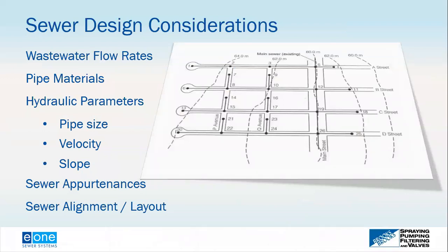When looking at design considerations, there are many similarities and differences between gravity sewer systems and pressure sewer systems. Key similarities include wastewater flow rates — the objective of any wastewater collection system is to move wastewater from point A to point B. Pipe materials are also often similar between modern gravity and pressure sewer systems. Hydraulic parameters such as velocity, flow, pipe size, and in the case of gravity sewer systems, the slope of the pipe, are all important because slope maintains proper velocity.